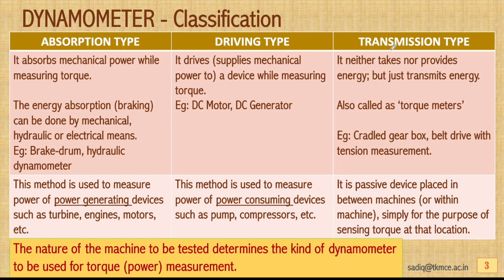Transmission type dynamometers neither take nor provide energy — they simply transmit energy from one device to another. These are also called torque meters. Examples include a cradle gearbox connected between two devices, or a belt drive with belt tension measurement. When power transmission happens there will be tension on one side and slack on the other, so the torque at that location can be identified. It is a passive device placed between machines simply for the purpose of sensing torque.